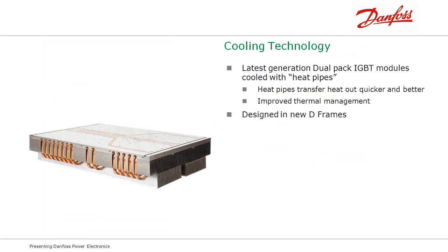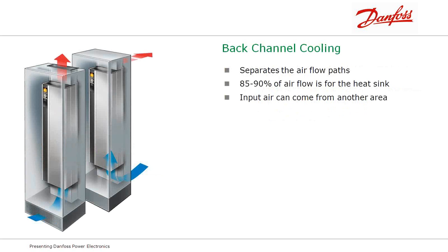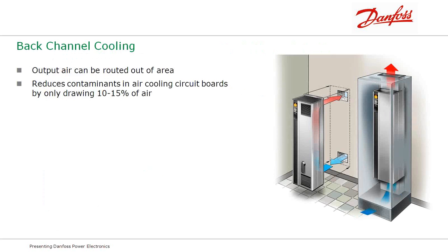We've done some great innovations on size in the technologies with our new D-frame series being a little bit smaller, really reduce the size using some very innovative heat pipe technology in the heat sinks, allowing you to dissipate the heat and get it out of the heat sink and out of the components so that they get longer life. That also allows us to separate the air paths by allowing the air to flow. 85% of the heat generated by a drive is in the heat sink. So by separating the electronics from that, you keep all that air from flowing through and across the circuit boards. You separate those two compartments.